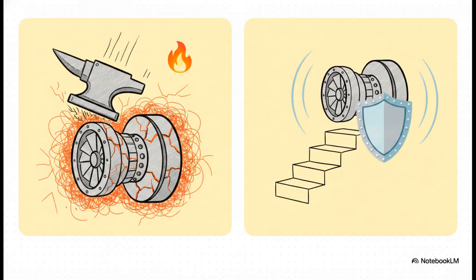Taking that shortcut and applying full load in one shot causes severe thermal shock. You'd literally be swinging temperatures across the hot section of the engine hundreds of degrees in mere seconds. That aggressive expansion of metals severely shortens component life, and it can honestly destroy the machine outright. The stepped 5 megawatt loading process is specifically designed to avoid this thermal shock entirely, protecting the engine by giving the internal metals time to expand evenly.